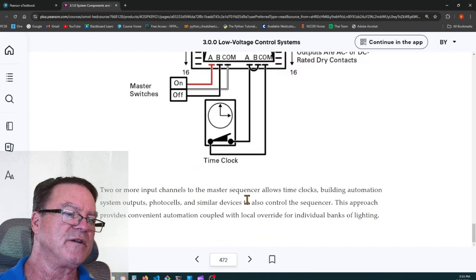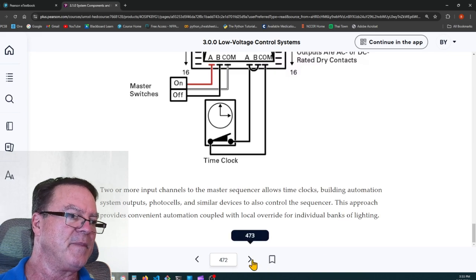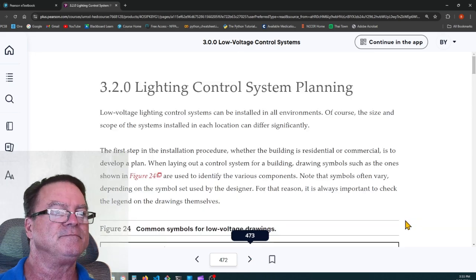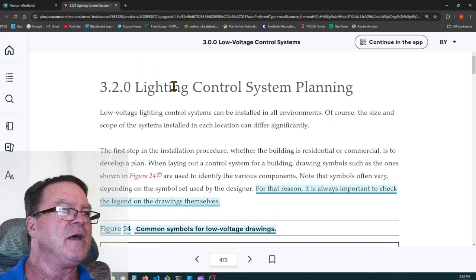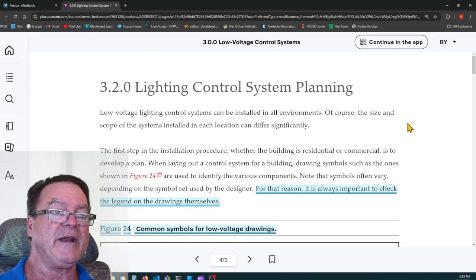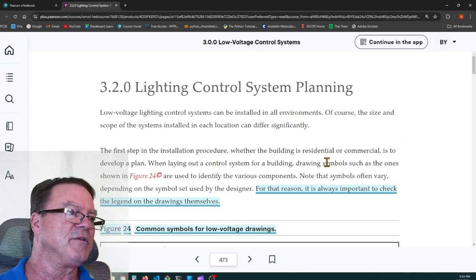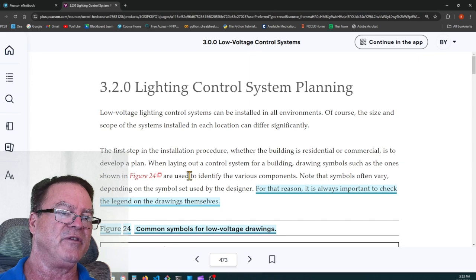Two or more input channels to the master sequencer allow time clocks, building automation system outputs, photocells, and similar devices to also control the sequencer. This approach provides convenient automation coupled with local override for individual banks of lighting. Lighting control system planning. First step in the installation procedure, whether the building is residential or commercial, is to develop a plan.